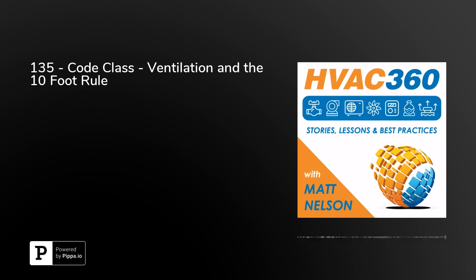Number 3 is that if it's 3 feet or more below a contamination source - and that's the very important key there, contamination source - then it can be within 10 feet. So basically, if your outside air is underneath your exhaust area or noxious contamination source area, it has to be 3 feet below, but it can be within that 10 feet. If it's on the same line, you need 10 feet of separation, but being 3 feet below allows you some separation instead. I assume they figure the noxious fumes are going to go up, they're more buoyant, so everything's going up. I think that's why they allow that exception.